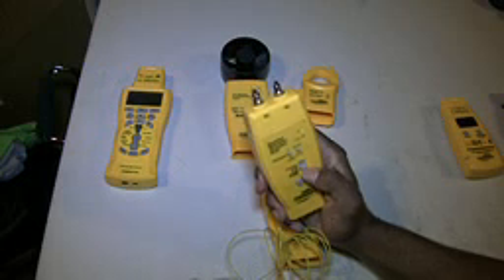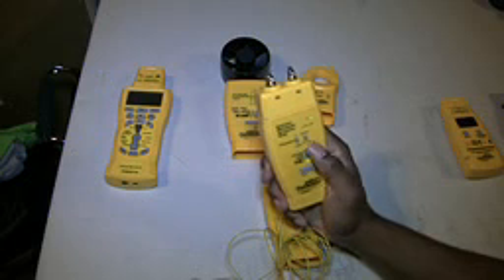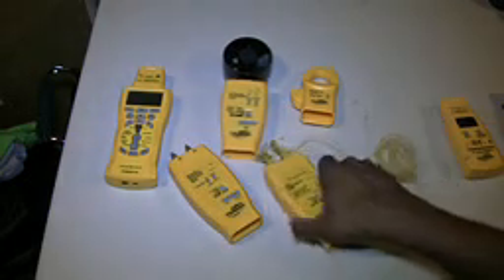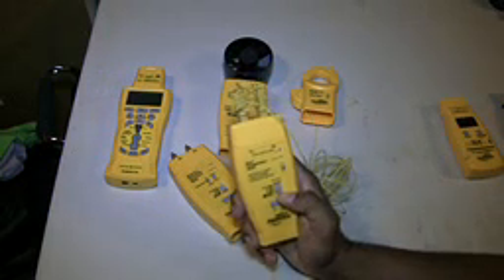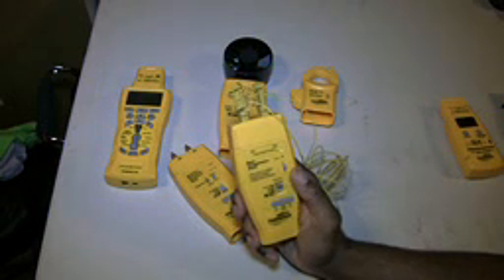With my manometer, I can only see one port at a time, or the difference between both ports at a time on the display. With my temperature head, I can only see one temperature at a time, unless I set it to T1, T2, which gives me the difference between both.